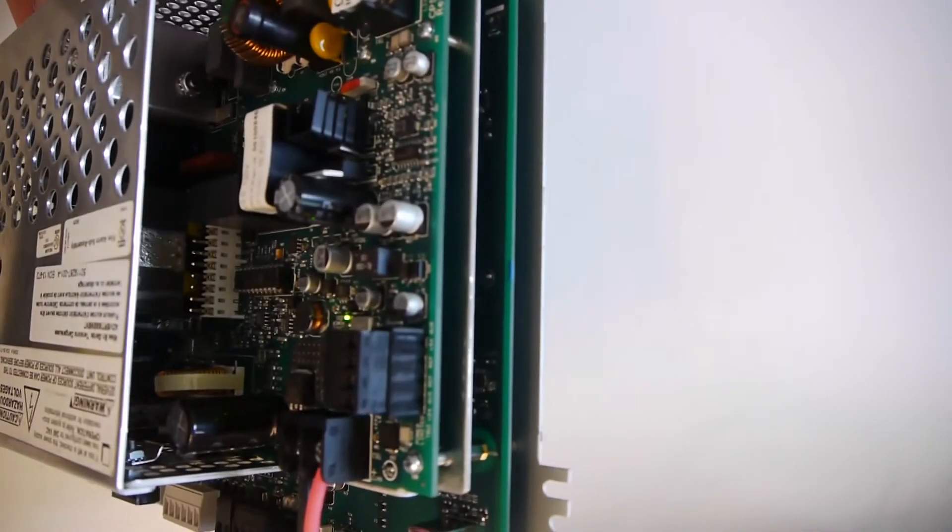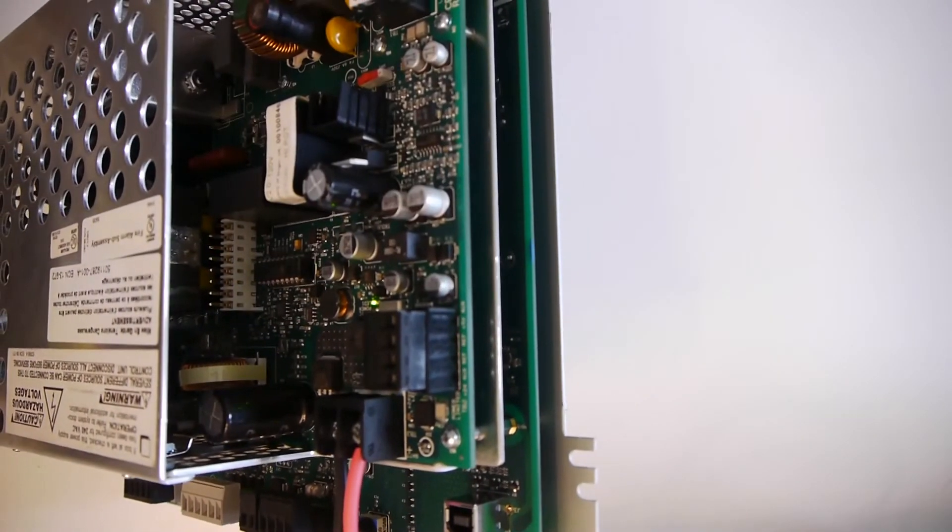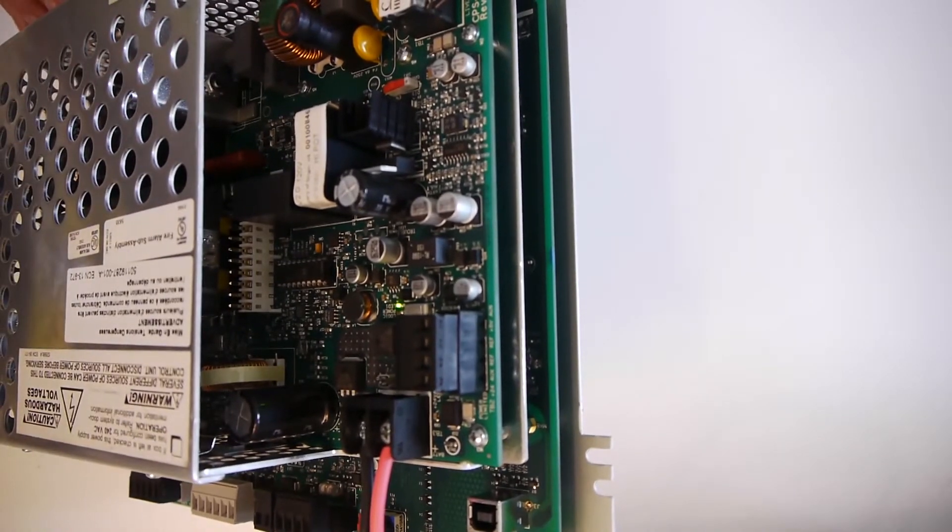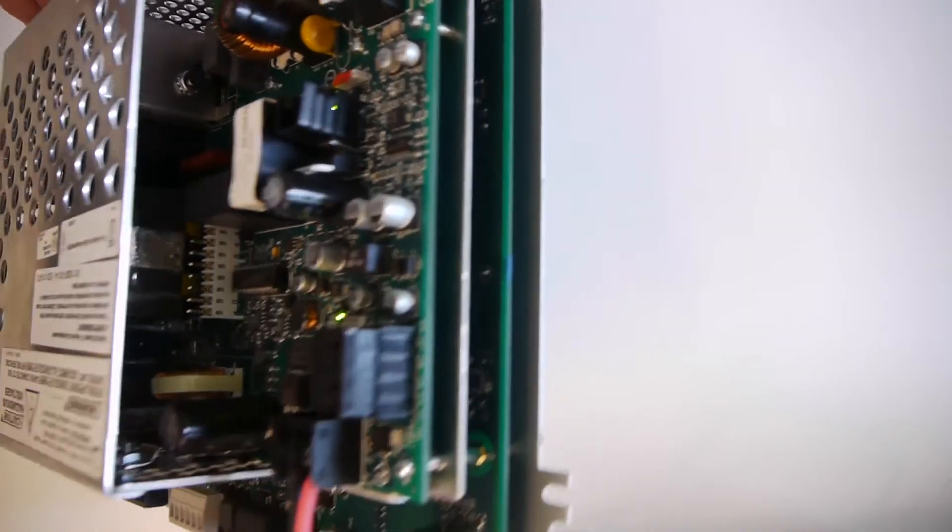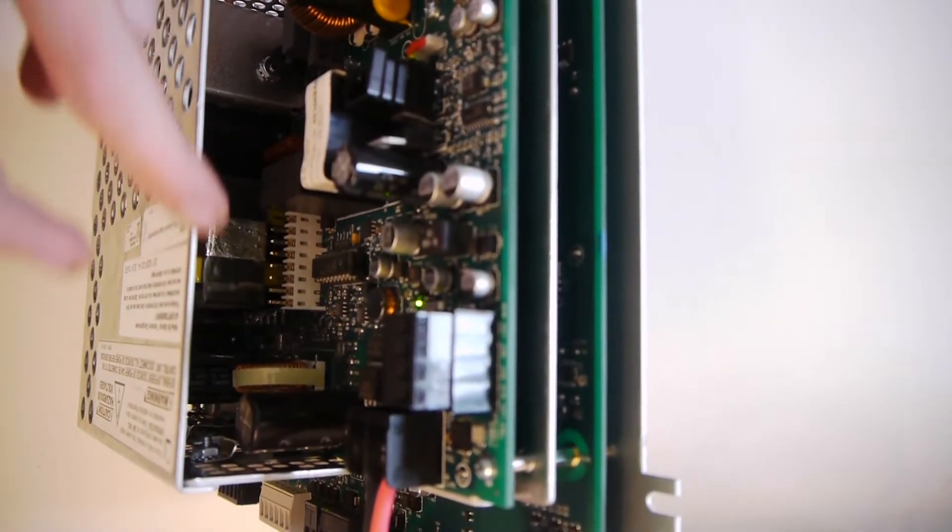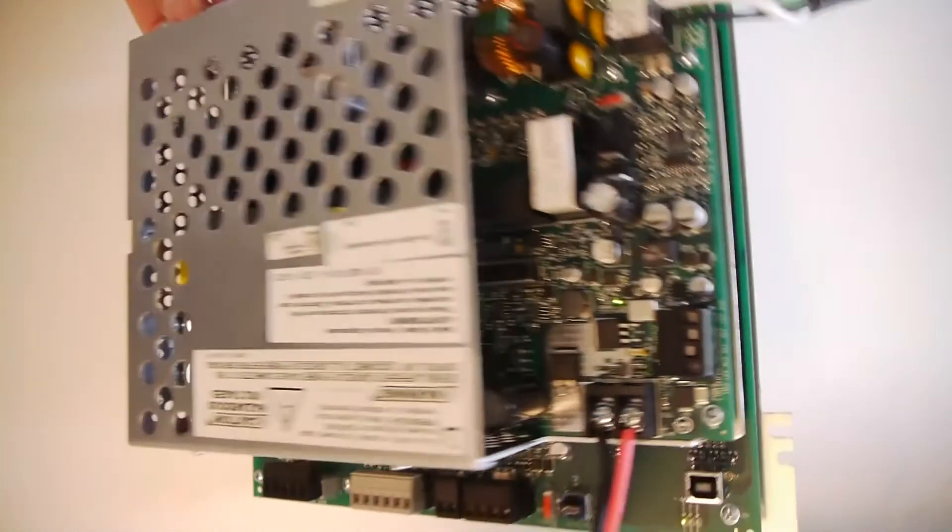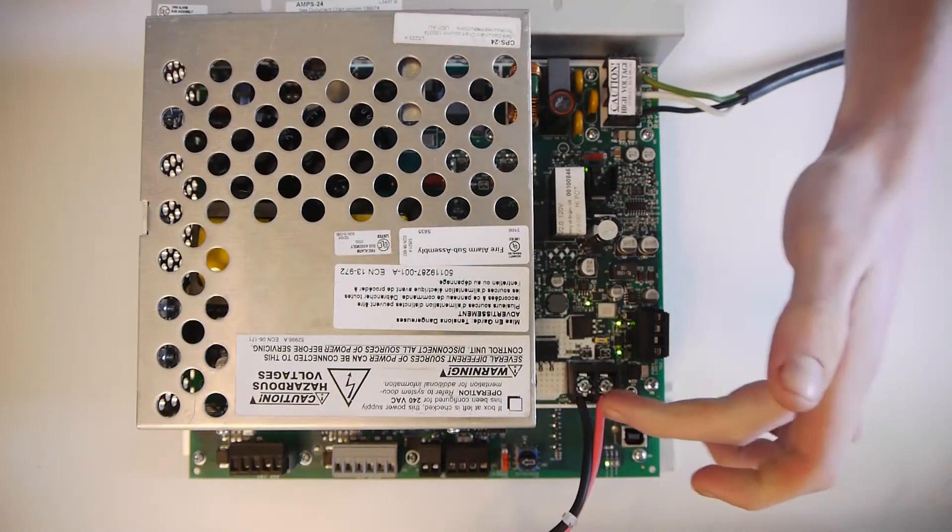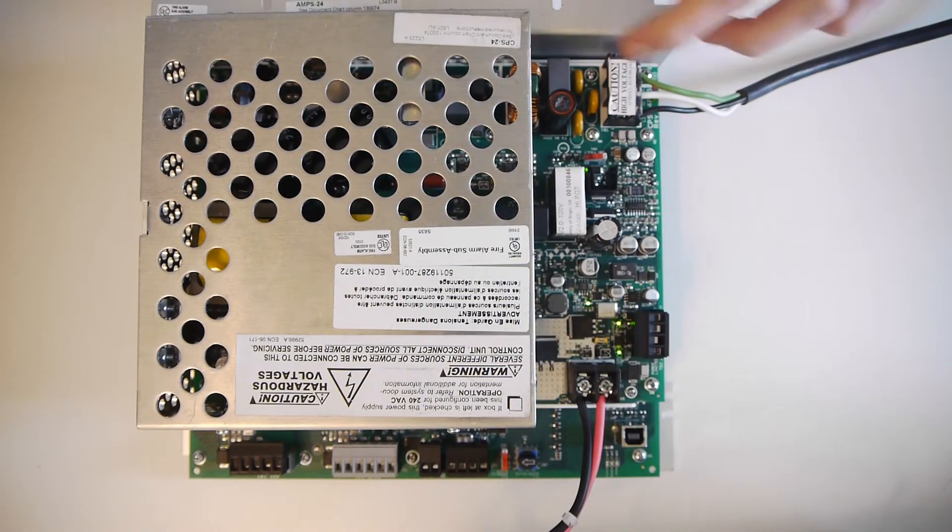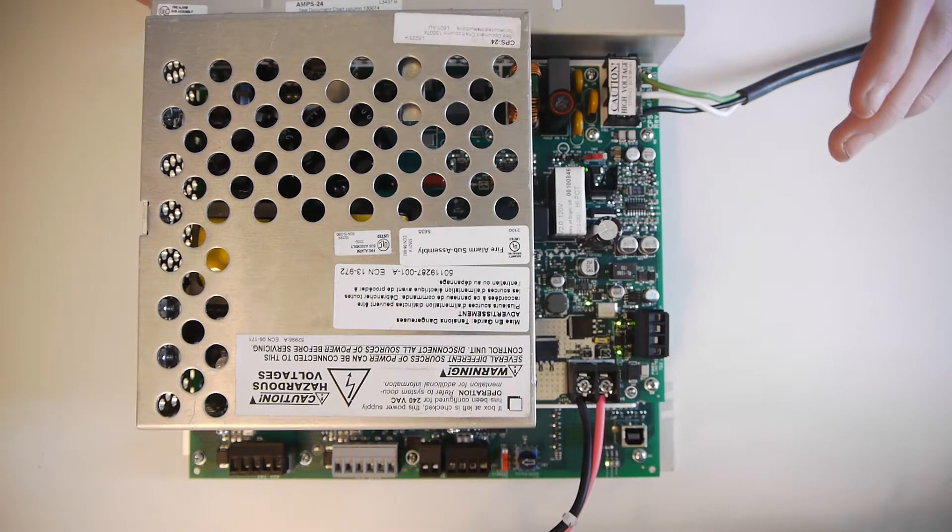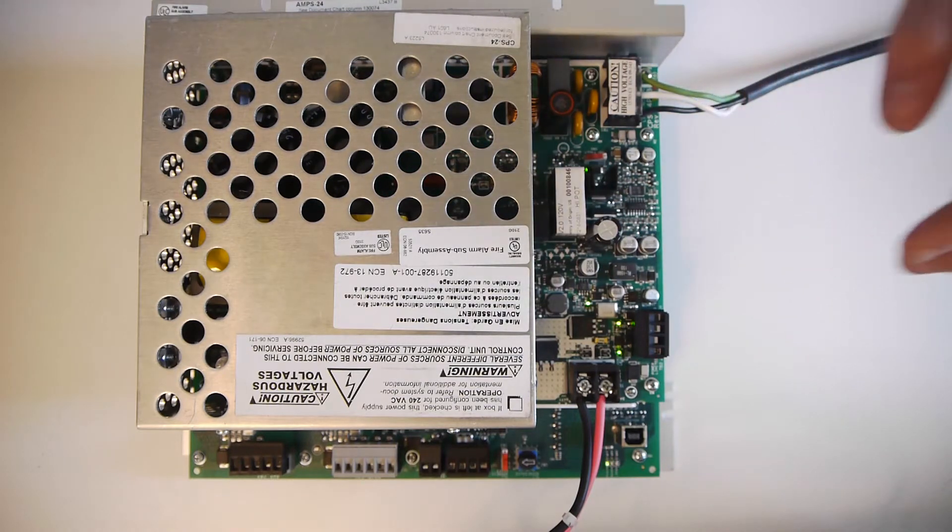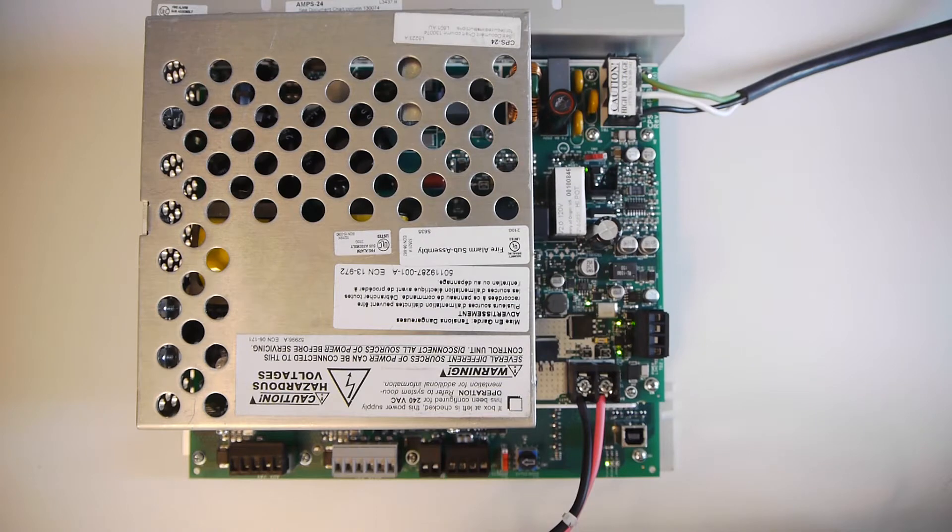So if I bring this up, you can see that there are two boards and there's an aluminum chassis attached to the bottom of the CPS board. To connect these two, there is a row of gold pins right there. And that's how the two communicate. You can see that the battery terminals and the AC power terminals are all on the CPS24. The CPS24 handles the battery switchover and the conversion between 120 volts AC and 24 volts DC.